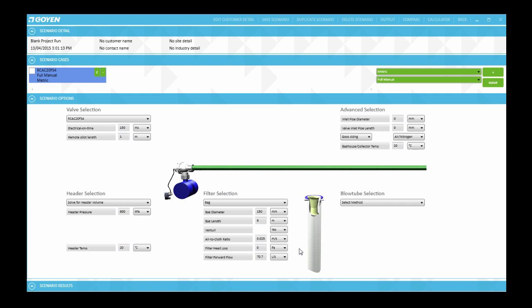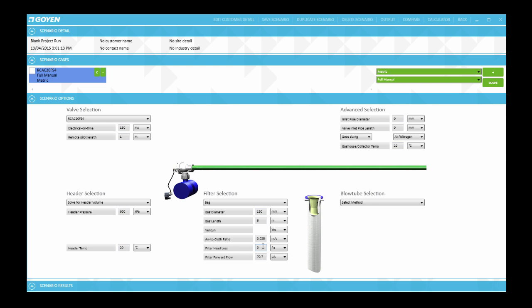Next the filter head loss also needs to be filled in. Normally this will be filled in immediately after the air to cloth ratio. But in this example it was to show that the filter forward flow rate has been calculated. So the filter head loss for a typical coal-fired boiler will be 1500 Pascals. Now of course this is the pressure drop between the dust collector, the dirty side and the clean side.